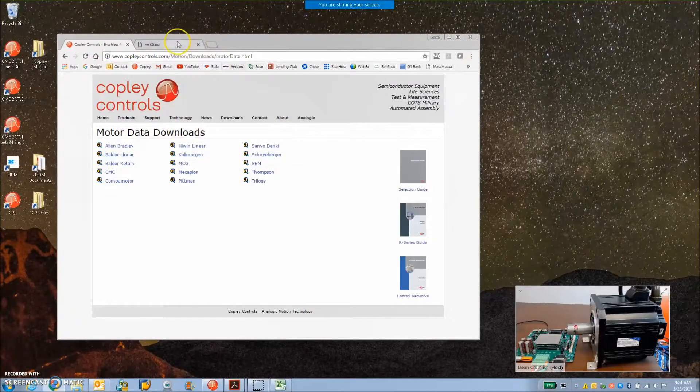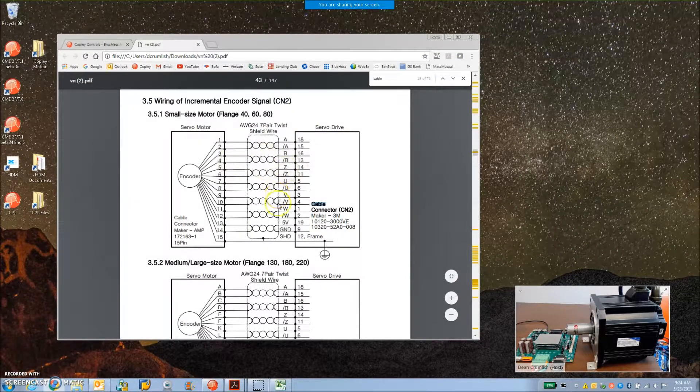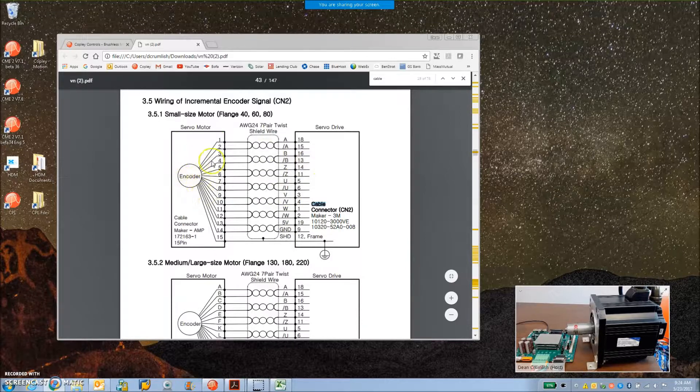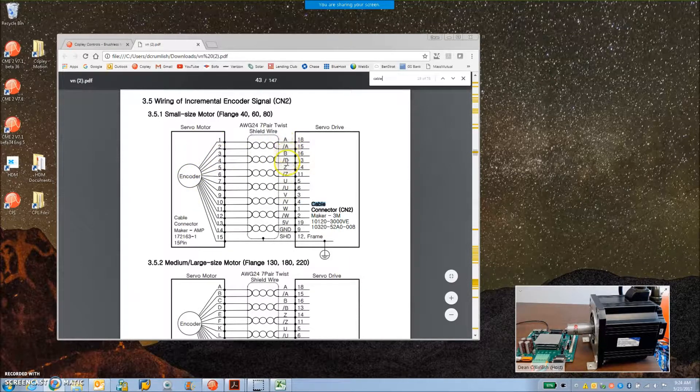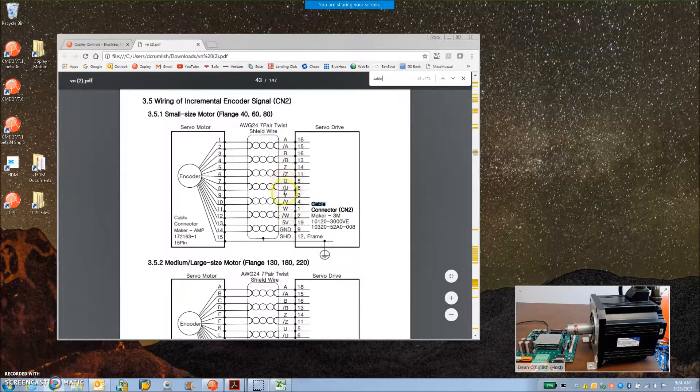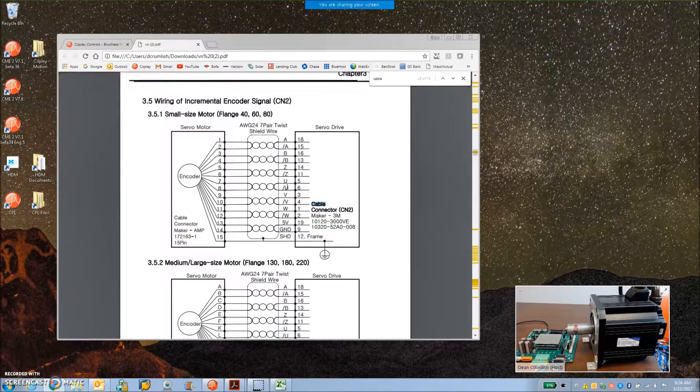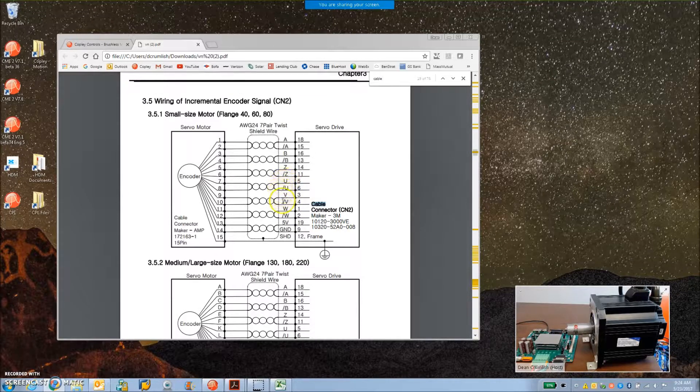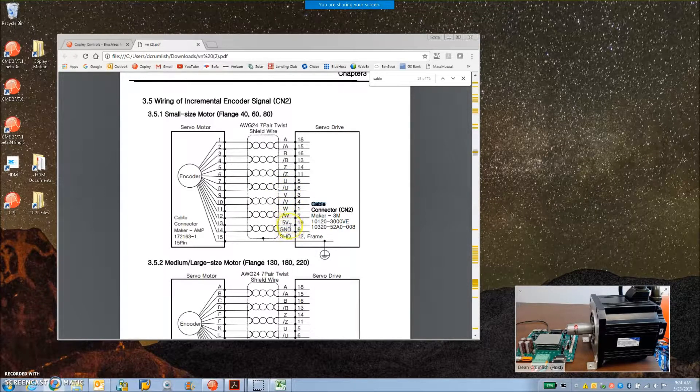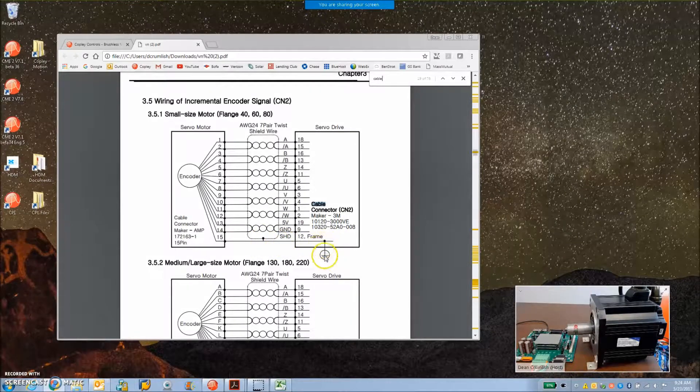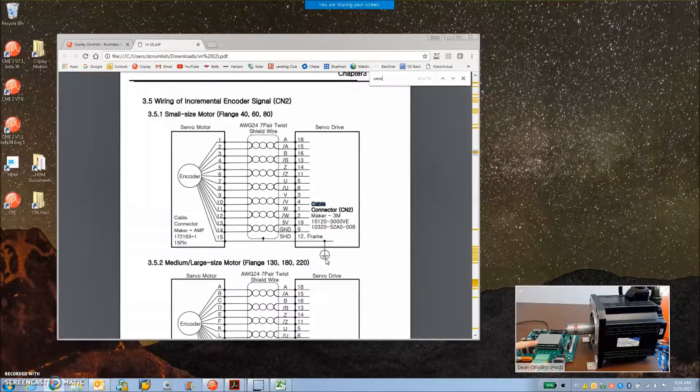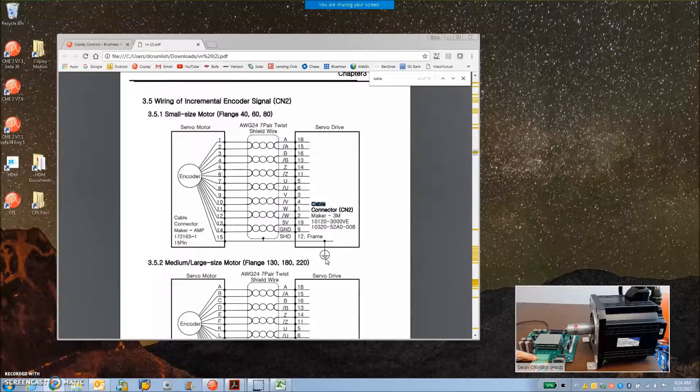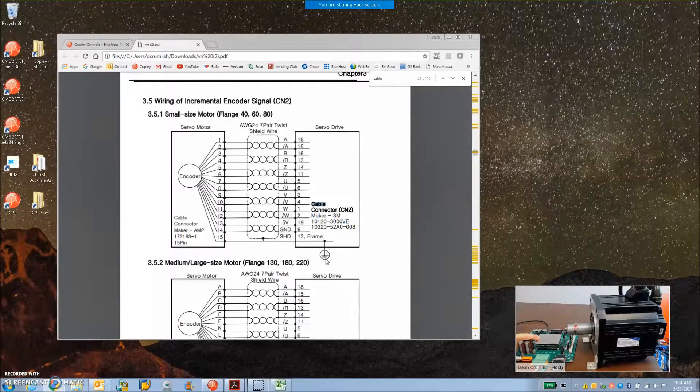We'll take a look at that. And then if you get the cable you'll have to figure out how to wire it. The encoder cable has incremental encoder: A, A not, B, B not, Z, Z not or index, index not. And there's UVW differential. We don't need differential, single-ended is fine, so just hook up the U, the V, and the W and don't do anything with the nots. There's a plus five and ground and a shield. Make sure the shield is connected to the frame earth. Make sure this power supply has a connection to earth close to the drive. Keep the distance as short as possible. This heat plate can also be connected to earth when it's mounted to the frame.